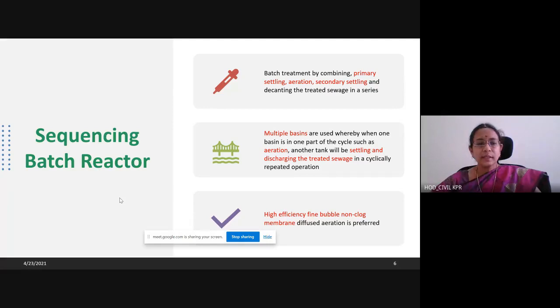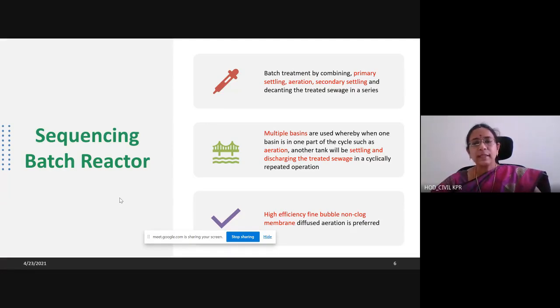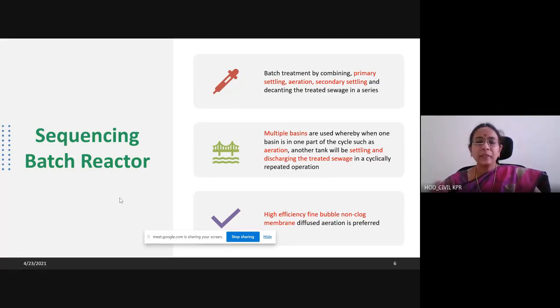The first one is the Sequencing Batch Reactor (SBR). An SBR combines two or three treatment components into a single unit, and two or three cycles are carried out in each unit before the water is let out for reuse. It is a batch process in which primary settling, aeration, and secondary settling are all carried out together. Earlier, these were separate components — primary settling separate, aeration separate, secondary settling separate — but here all are put together in series and called a single batch.